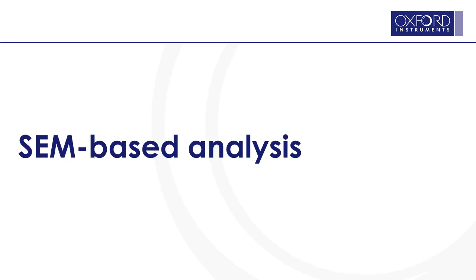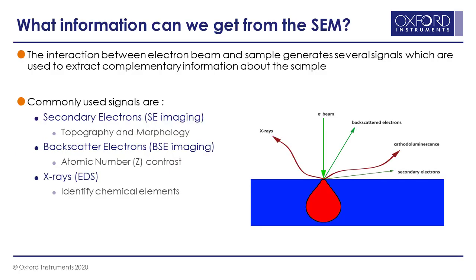SEM-based, or scanning electron microscopy-based, analysis — what information can we get from the SEM? In the SEM we have an electron beam that is focused onto the sample surface, and the interaction between the electron beam and the sample generates a range of signals which we can use to extract information about the sample. Some of the most commonly used signals are secondary electrons — electrons knocked off the sample that give us information about topography and morphology — and high-energy backscattered electrons, which have interacted with the nucleus and thereby give us atomic number contrast, showing where we have density variations, heavy elements, and light elements. The interaction also generates X-rays that are characteristic for the elements in the sample, and by detecting and analyzing those X-rays we can get information about the chemical elements present.